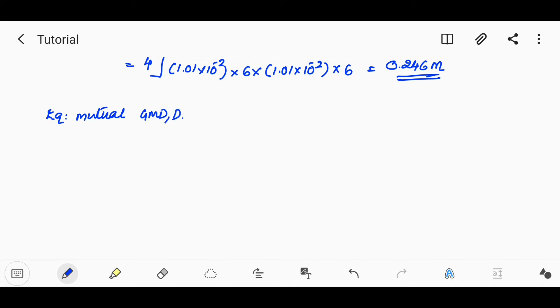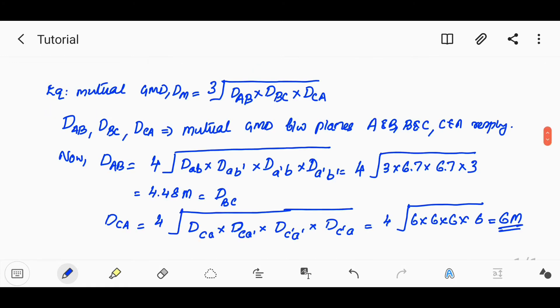Now, the equivalent mutual GMD Dm = (Dab · Dbc · Dca)^(1/3), where Dab, Dbc, and Dca are the mutual GMDs between phases a-b, b-c, and c-a respectively. Dab is found as the fourth root of DAB · DAB' · DA'B · DA'B'.